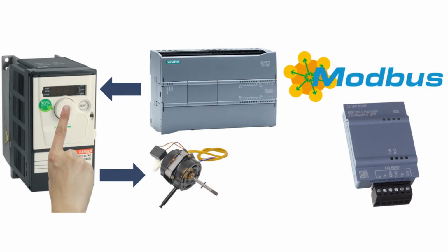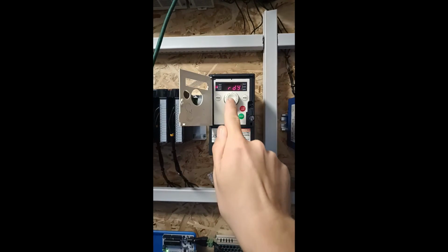In this video we will go through how to run a Schneider ATV312 VFD using the Modbus RTU communication protocol from an S7-1200 PLC. First let's go through how to do the settings on the VFD. First we want to go to the COM parameter.